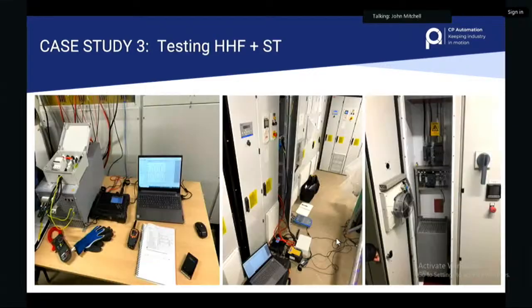They were having all kinds of problems, which I won't bore you with today since it's a whole topic on its own. But the main problems we were there to fix were transformers having gas in the oil results, which meant the transformer's warranty was being invalidated. In addition, the ABB drives, which are active front-end drives, were causing problems with the generators.